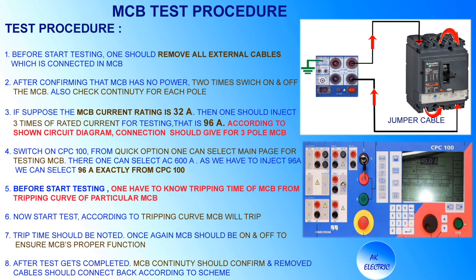Switch on the CPC100. From the quick option, select the main page for testing the MCB — you can select up to 600 ampere. As we have to inject only 96 ampere, select exactly 96 ampere from the CPC100. Before starting the test, you have to know the tripping time of the MCB from its tripping curve. Now start the test; according to the tripping curve the MCB will trip. Note the trip time, then switch MCB on and off once more to ensure it is functioning properly.